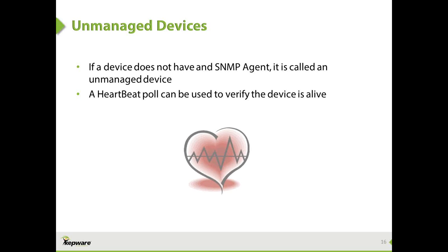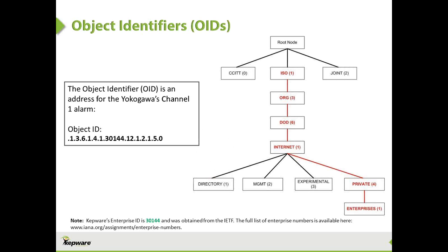I have one question. It says, does the MIB reside on the PC? So a MIB resides local to the SNMP-enabled device, so it's on the device memory, and you also need to have it on the computer that the SNMP manager is installed on, so that the SNMP manager can use it to look up things in that device.